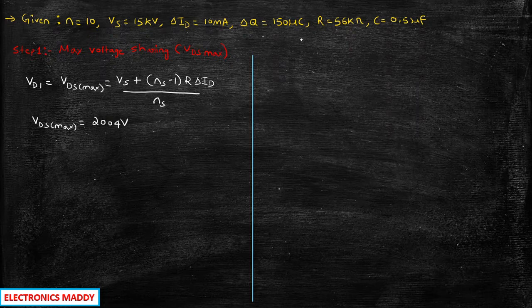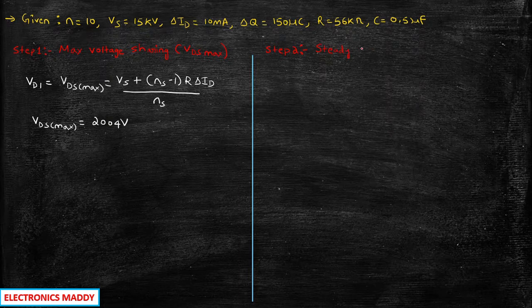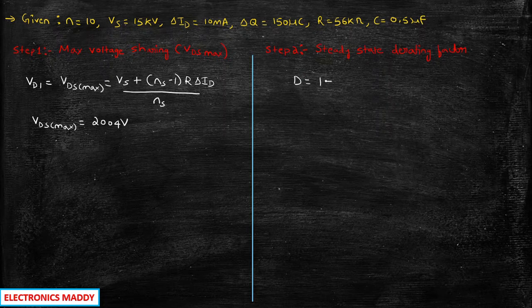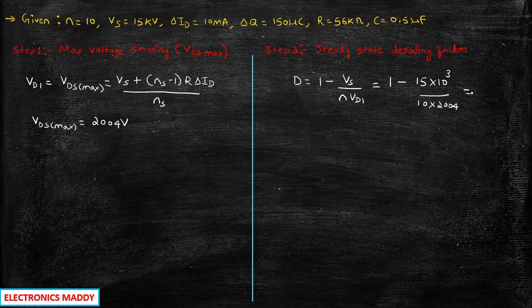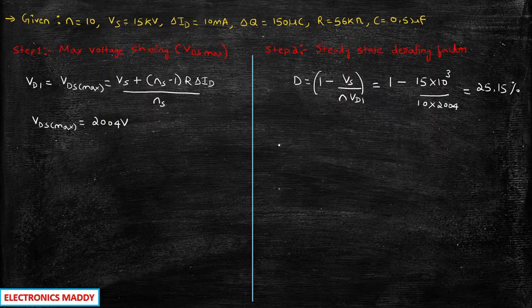Step two is to find the steady state derating factor. The standard formula is: D equals 1 minus Vs whole divided by N into Vd1. Substituting Vs equals 15 kV, N equals 10, and Vd1 equals 2004, and multiplying into 100, you will be getting the value equal to 25.15 percent.